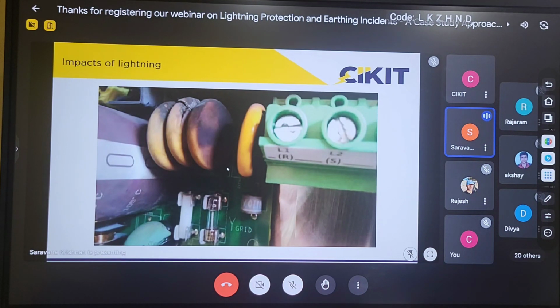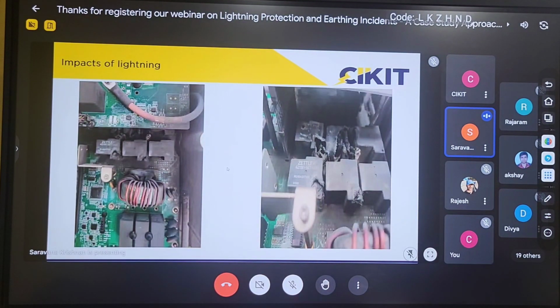Fuses won't provide protection against surges that are due to lightning. The fuses, MCBs, circuit breakers and voltage stabilizers which we have won't protect the electronic equipment from surges. That is the reason we have to go for a separate device. These are the damages caused by lightning impulse surges. It is very dangerous, similar to normal lightning damage. We have to provide proper protection because nowadays we are using more sensitive devices. If these sensitive devices are not protected properly, it will result in huge loss.